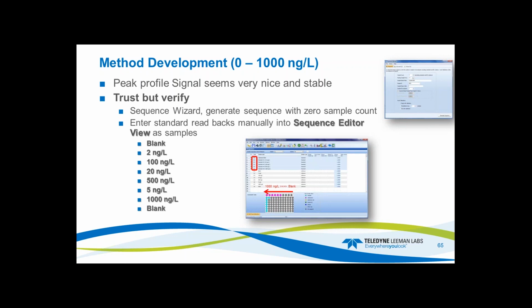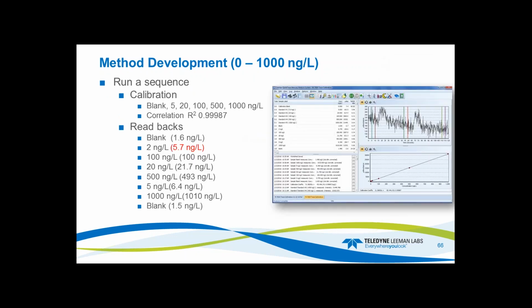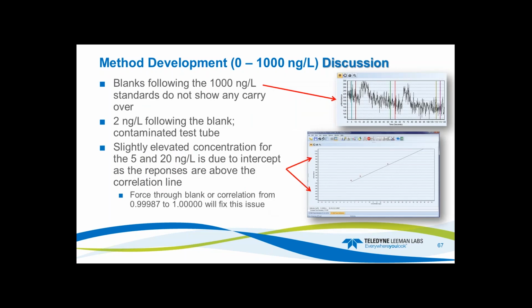Then I read back my blank, my 2, 20, 500, 1,000, and a blank. On the readbacks, my calibration gave me 0.9987. That's pretty good. I had a problem with the 2 coming in at 5.7 nanograms, but the rest of them came in pretty good. 100 nanograms was 100, 20 was 21.7, 500 is almost bang on, the 5 is a little bit high, the 1,000 is bang on at 1,010, and the blank came in a little bit high at 1.5. The blank following the 1,000 didn't show any carryover, so what's my problem?